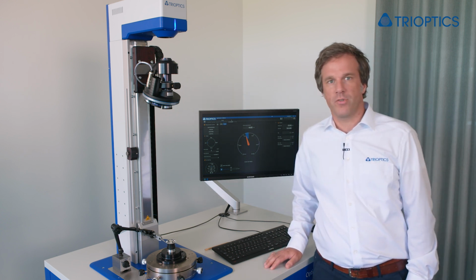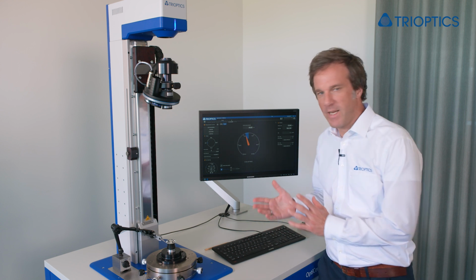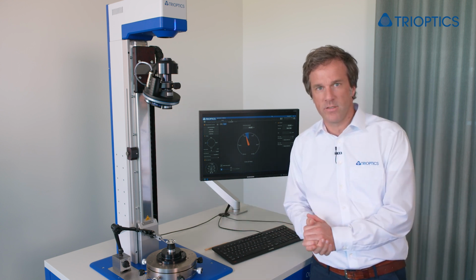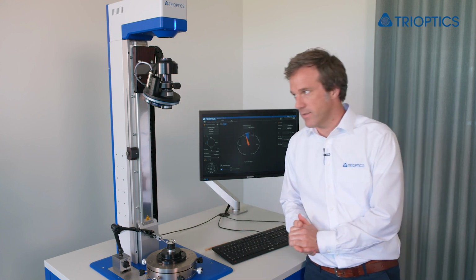What I want to show you today is how the software helps us in aligning a workpiece to the instrument spindle axis. This is something that is done hundreds of times a day in optics manufacturing. Here I will illustrate this manual alignment process for a lens that sits on a vacuum chuck. For example, this alignment is required when you want to test or align centration error with respect to the lens outer diameter.